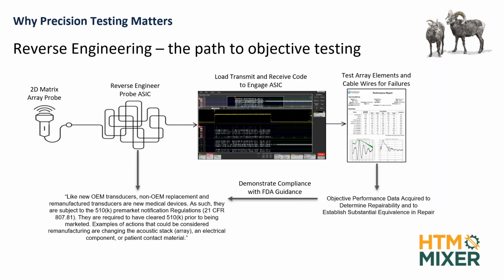It was controlled by an ASIC up in the housing, so we needed to reverse engineer that probe ASIC, what turned it on, what its control lines looked like. This is all what popped out on the other side. Our cryptology guy would freak over this. So we get all of that data here, and then we create a device, a machine that can go in and test array elements and cable wires for failures. So when we plug the probe into our testing device, it thinks it's hooked up to the ultrasound machine and it starts transmitting. And then we collect all of the data here, confirm everything is working. So then we have to have objective performance. We demonstrate compliance with the FDA guidelines. And here's what they were saying, okay?